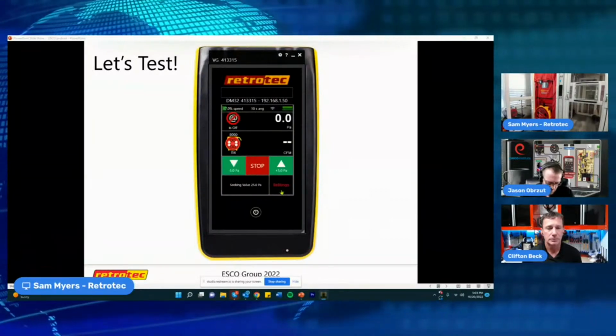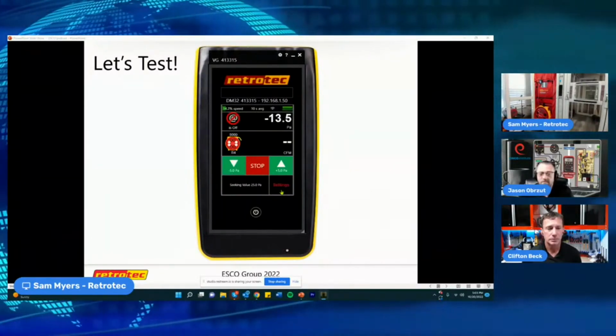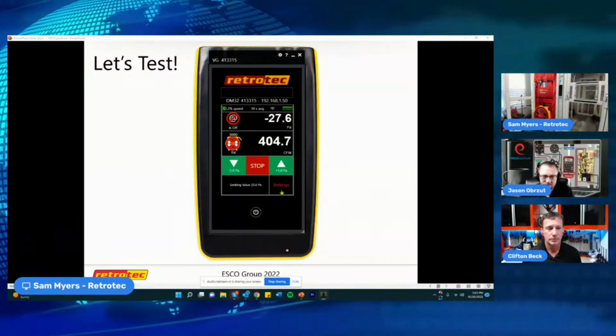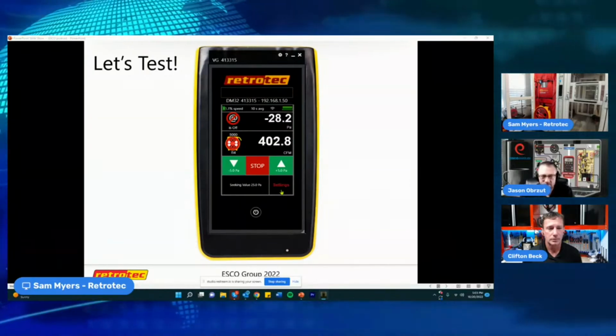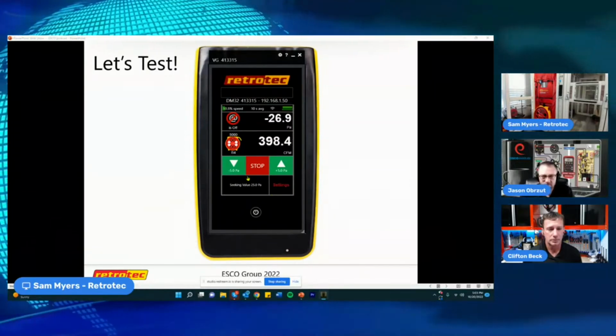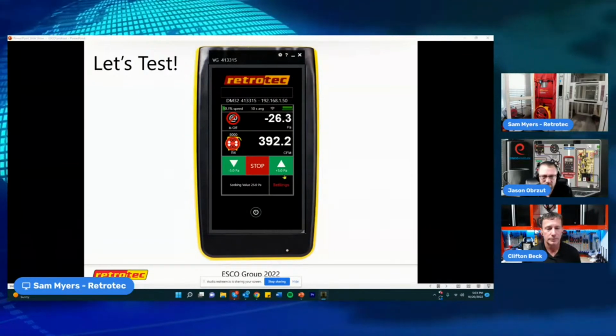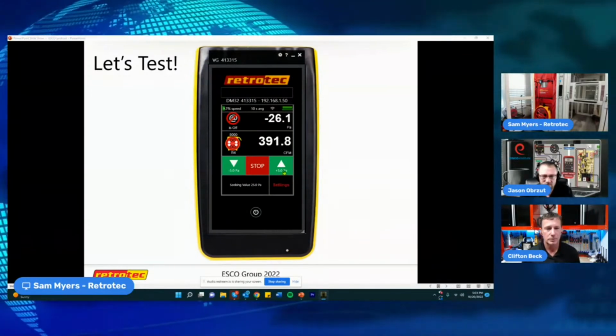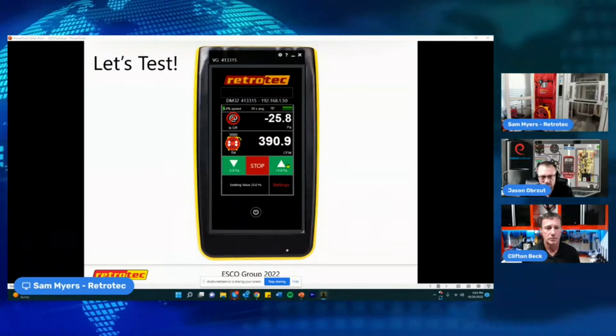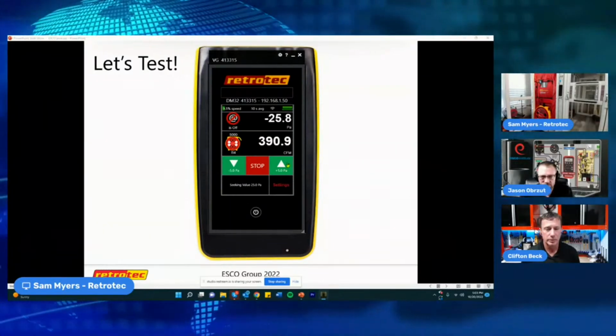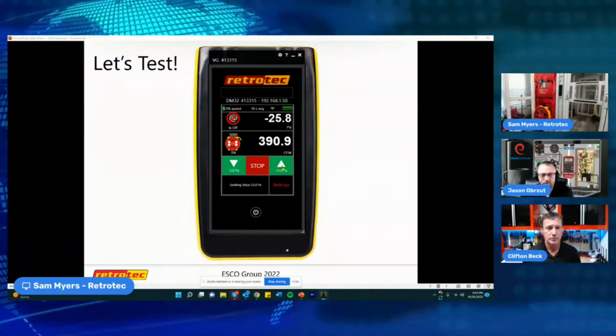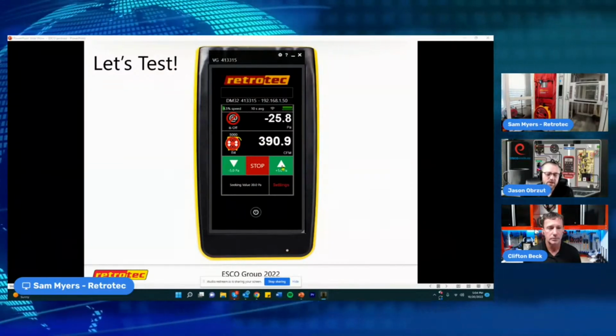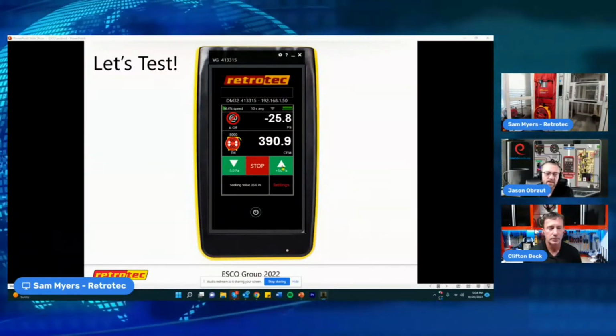So you hit set, and now you hear that fan kick on. The fan is running, seeking that 25 Pascal target. We've got these green jog buttons here to go up 5 Pascals. So we have it seeking 25, but if I walk around and everything looks good, I can just tap this until I get to 50. So I don't have to manually adjust this, I just put a number in and the fan seems to get there by itself.